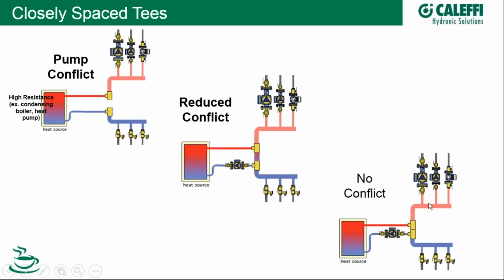Now, a rule of thumb for how closely you should space these T's together. If your supply piping, in this case, is diameter D, you want to make sure your center to center connections on your primary are no more than approximately 4D, 4 times the pipe diameter. Then you should be in real good shape. The other thing on your secondary, to minimize any pump conflict, is you want, as you can see here, very generously sized headers. Okay, they look pretty thick there.